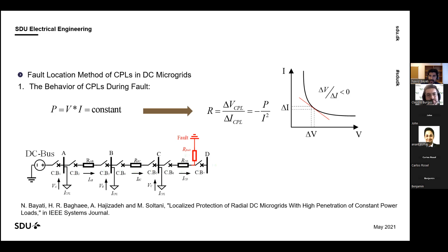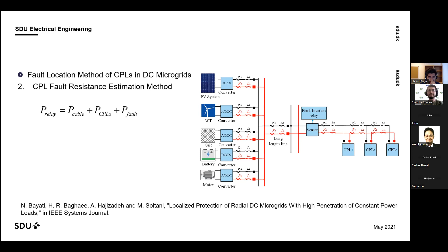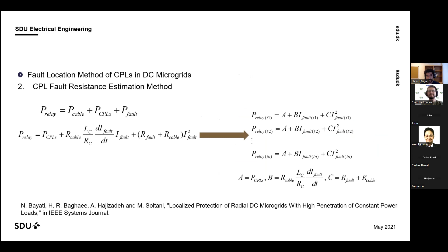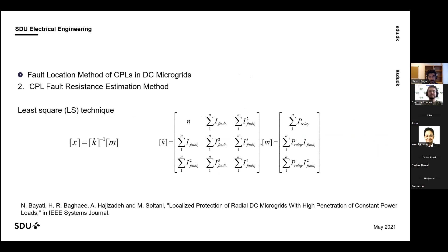Here we have a microgrid, and we propose a method to use a sensor from the main bus that's connected to different CPLs. Here we can see the PV system, wind turbine, grid, battery, and motor, all connected to each other. So we use the sensor in the main bus, and some equations based on the constant power loads' behavior, to estimate the location of the fault. Here are the equations, and we use an estimation method to do that, using the least square technique.